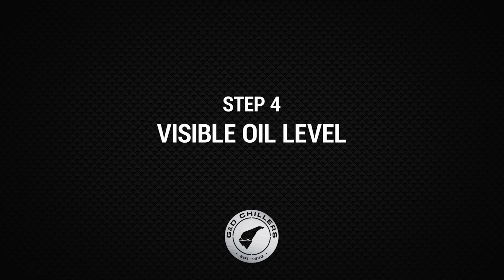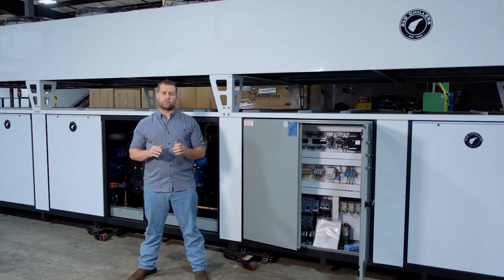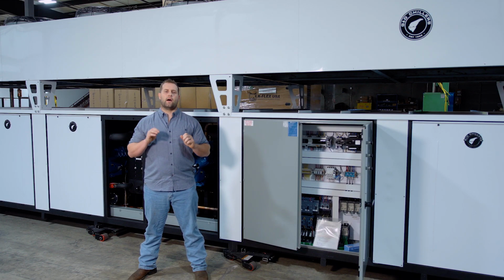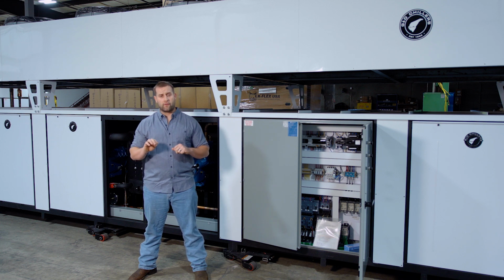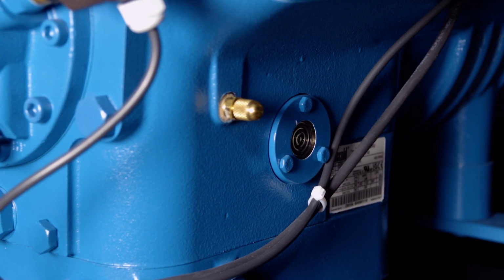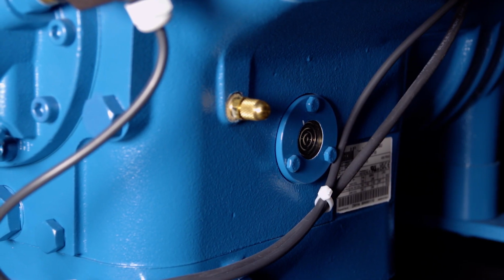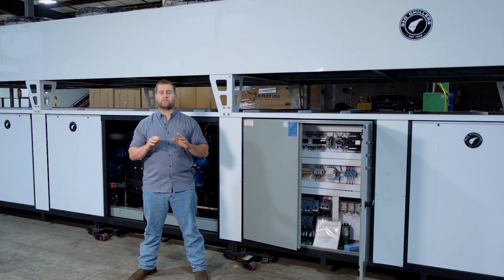So the next step on the startup of a G&D unit is verifying oil levels. You want to get your crankcase heaters energized by turning power on to the chiller and leaving your door switches off. You know the crankcase heaters have been on long enough if you can go to the compressors and see visible lines in the sight glasses. Once you see visible liquid lines in the compressor sight glasses, you're good to go on to the next step.